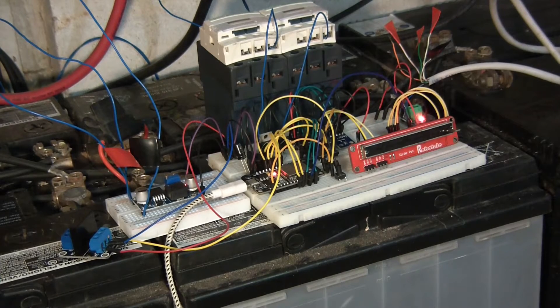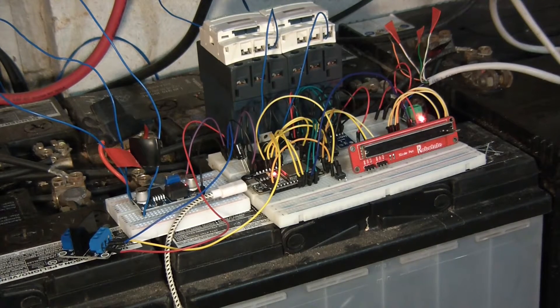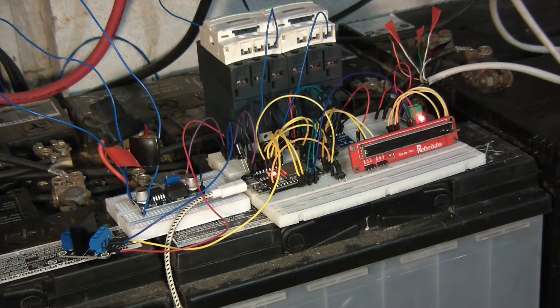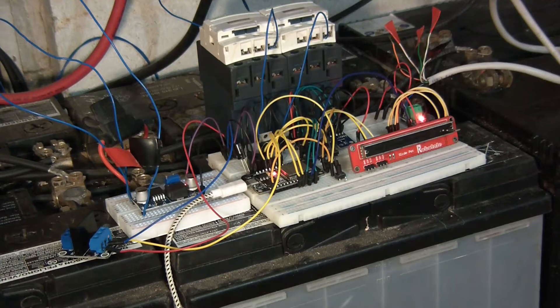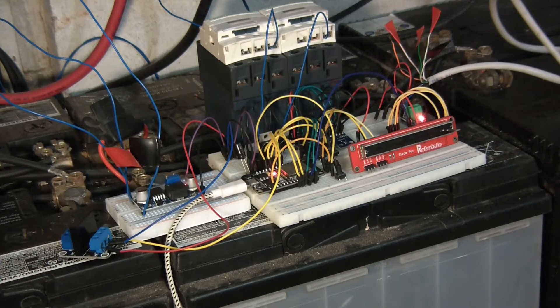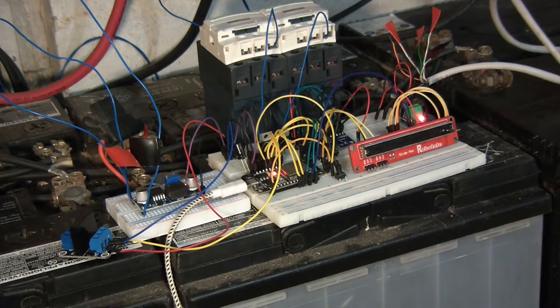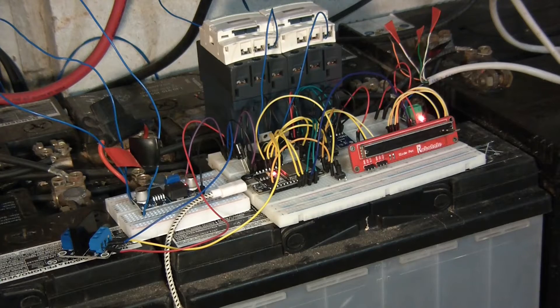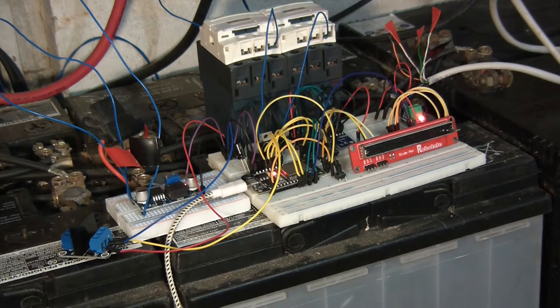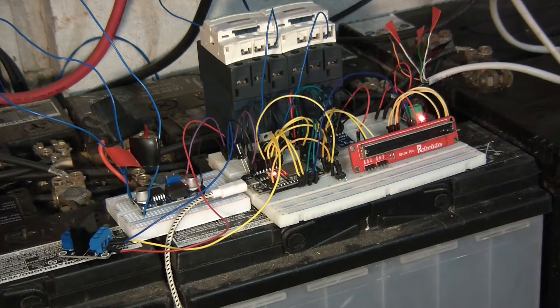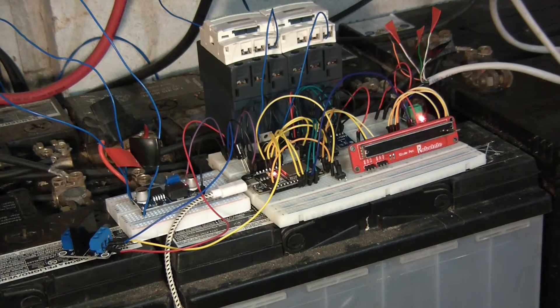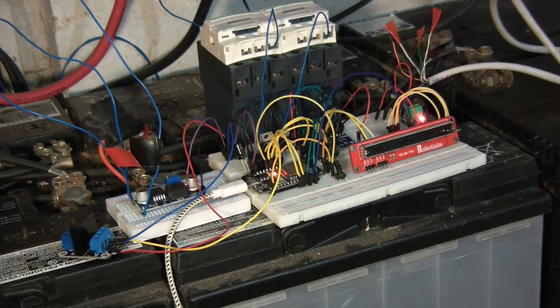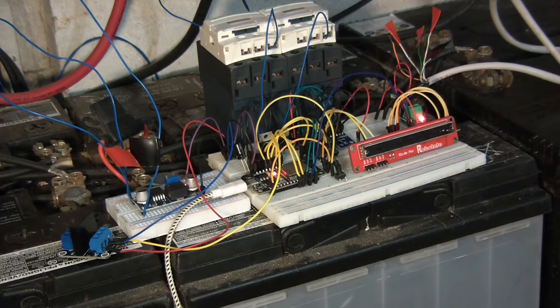What data does this thing log then? Well, data it logs are PV voltage, so that's the solar voltage, PV current or PV amperage, which is the current being drawn from the panels. It stores battery voltage and battery charge current. So when it comes in through the charge controller it gets stepped down and of course the current will go up. If you get an amount of wattage and you lower the voltage, the current will go up for the same amount of wattage.